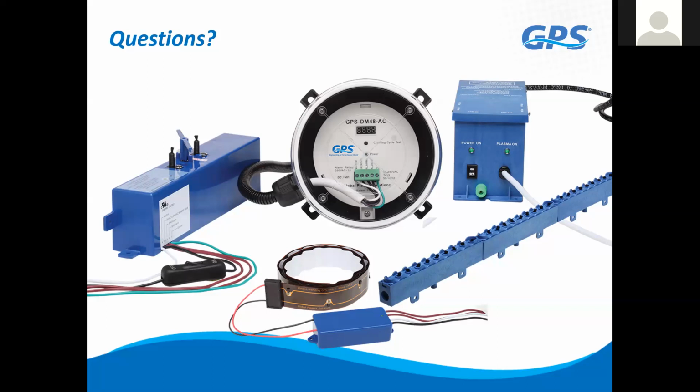Does the GPS unit get turned off when the unit is turned off? That is personal preference. You can power it 24/7, 365. The reason we can do that is because there's no odors being generated. A lot of times when you have, let's say, a PCO type product that's producing ozone, you will have ozone building up in the fan section when you're cycling. Then upon startup of the fan, you'll get a burst of ozone into the occupied space. With us, you can leave it powered 24/7, or you can cycle it with the fan. It doesn't really matter. It's personal preference.